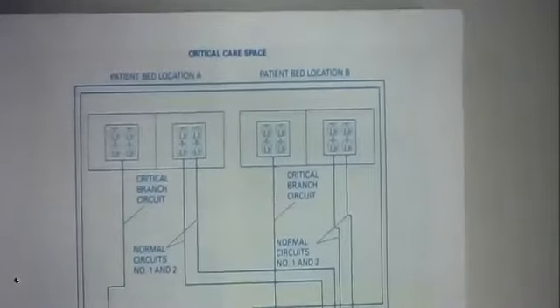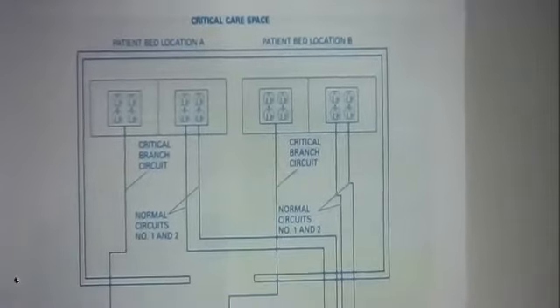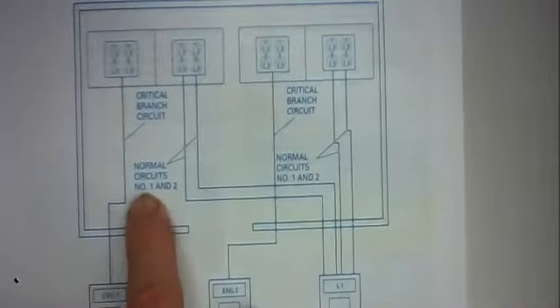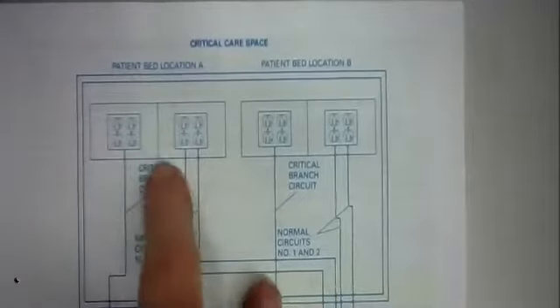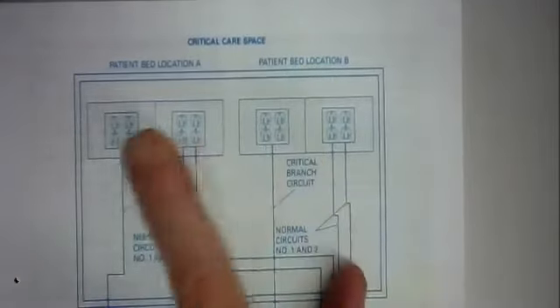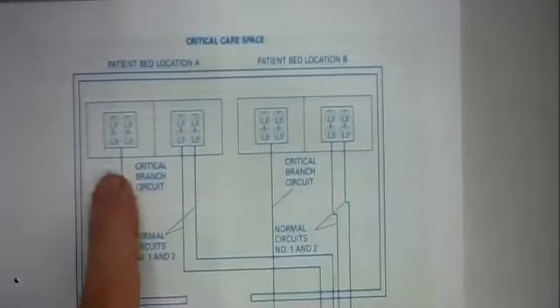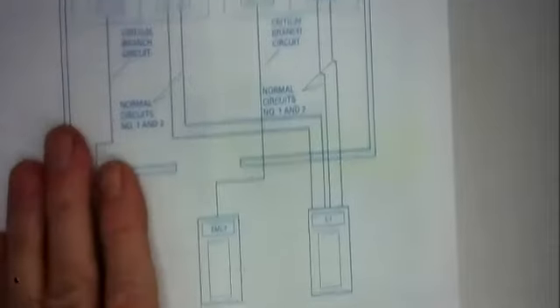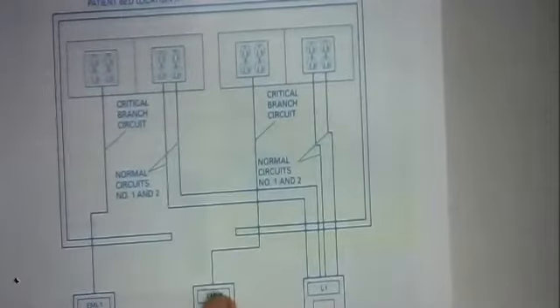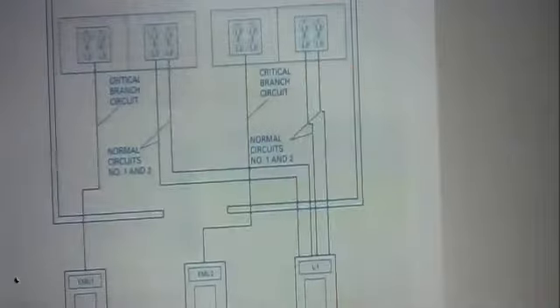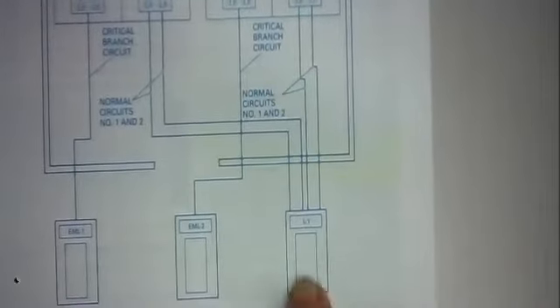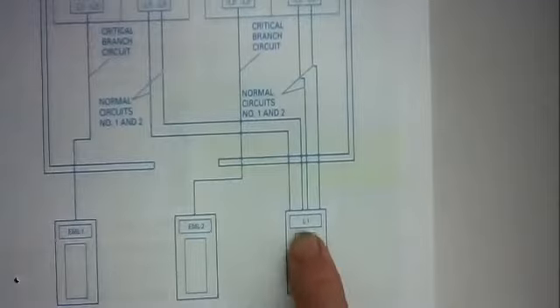Okay. No, I'm sorry, that's the operating room. This is 16 receptacles, 4, 8, 12, 16. So I've got bed number 1. Here's patient bed location A, patient bed location B. They both have 8 receptacles, 4 of which are going to emergency panel 1, 4 of which are coming from emergency panel 2, and 8 of them coming from the normal low voltage panel. Low voltage being 120/208, high voltage being 277/480.